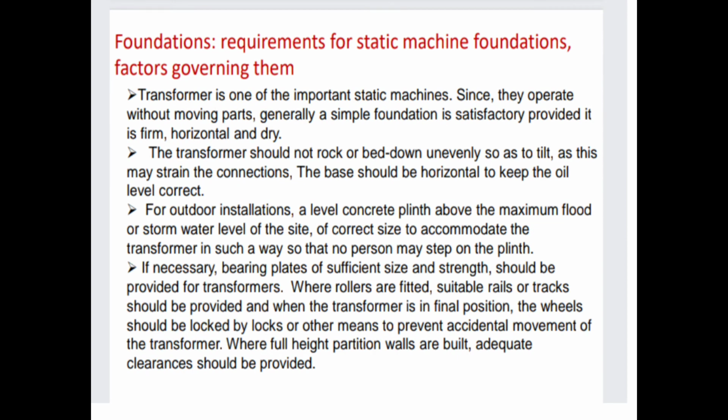So, foundation requirements for static machine foundations, factors governing them. Transformer is one of the important static machines. Since a transformer is a static machine and operates without moving parts, generally a simple foundation is satisfactory, provided it is firm, horizontal and dry.